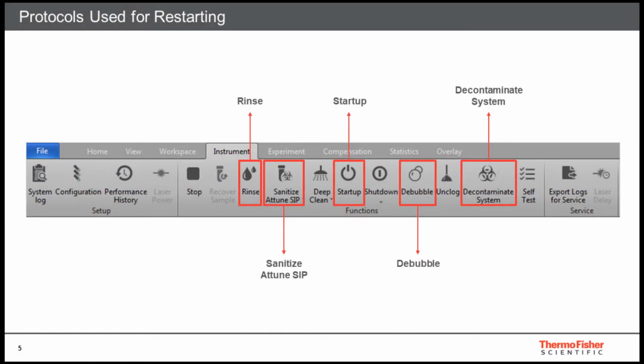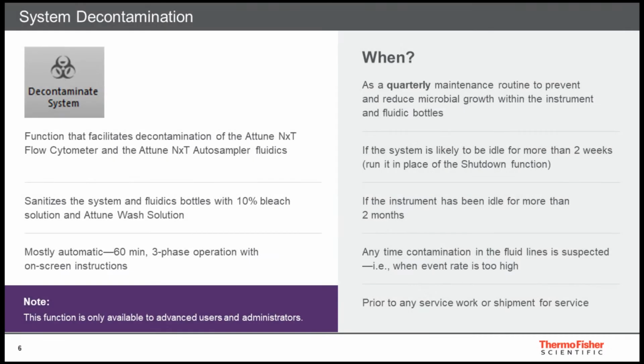Fluidic function scripts that will be used in the restarting procedure are startup, decontamination system, debubble, sanitize Attune SIP, rinse, among other scripts. Starting with the system decontamination script, we recommend running this script quarterly for thorough cleaning of the system. Unlike other scripts where bleach or other decontaminating solutions only run through parts of the cytometer where samples travel, this decontamination script decontaminates every line in the system. The process takes about an hour and consists of 3 parts or phases: sanitize, rinse, and refill.